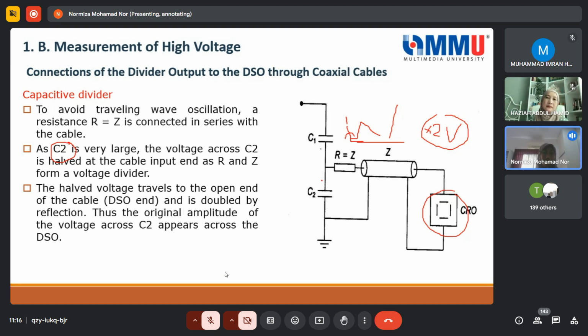So it's the same thing here. But because of the manufacturer, it normally comes with the cable with R equals Z, which they included here. So the voltage appearing at this oscilloscope will be half. But because of the nature of the reflected voltage, which is times 2, half times 2 becomes 1. So that's why, when we use the capacitive divider, what appears on the oscilloscope, we do not have to multiply or divide by 2 anymore.